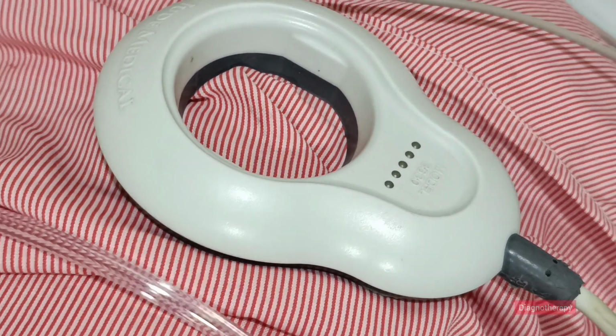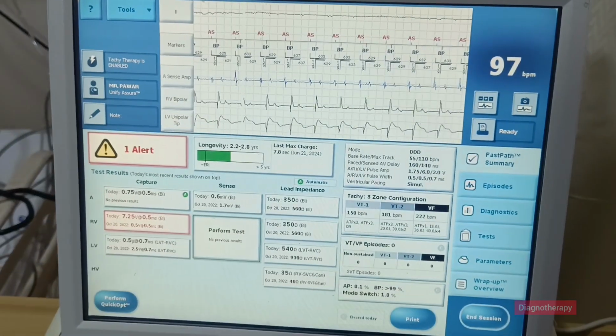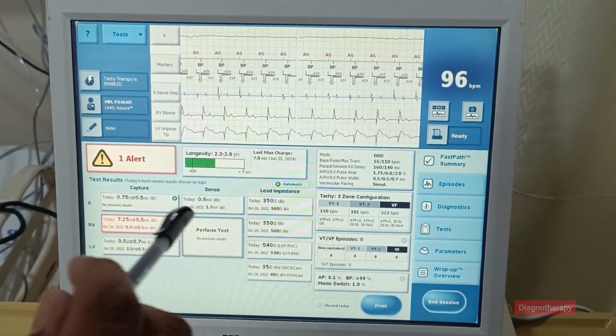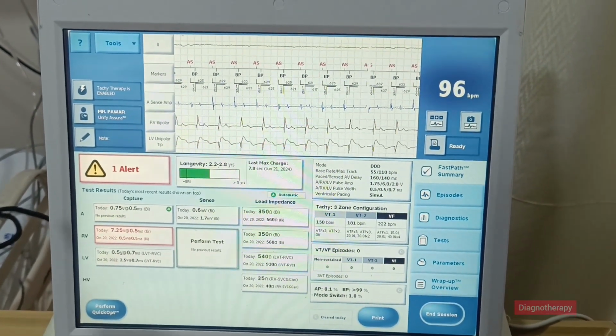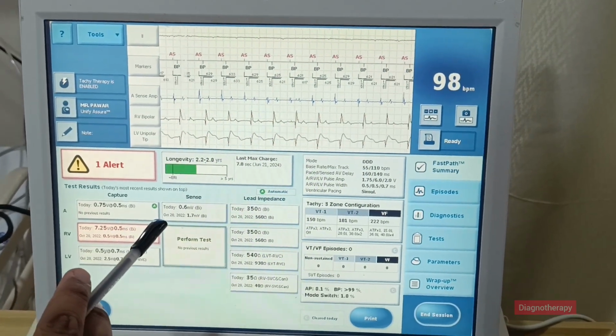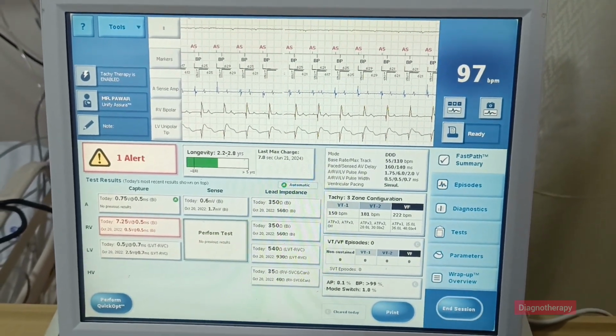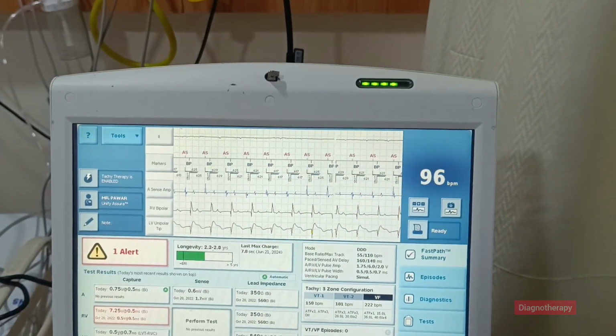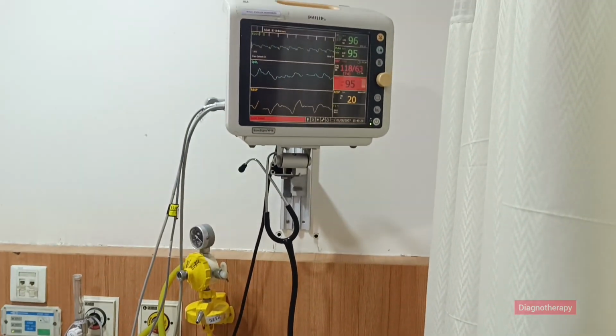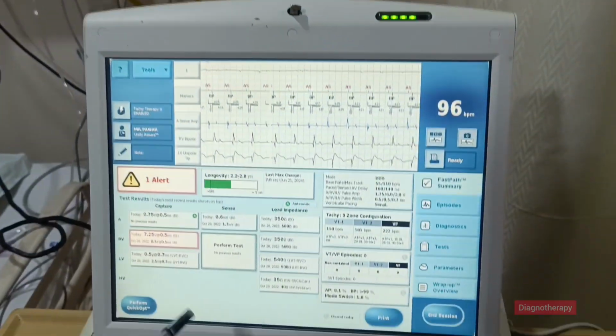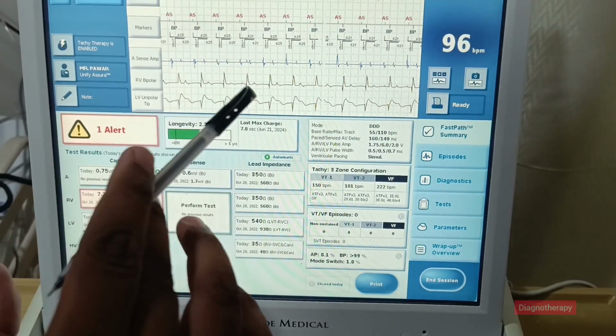From this transducer, the data is collected and we can see the different readings on the screen. When the transducer is attached, it shows all the data and parameters of the patient, when it was connected, whether any major event has occurred or not, or different types of ECG variation. We can also see the same thing in the patient monitor. This device checks the lead impedance.